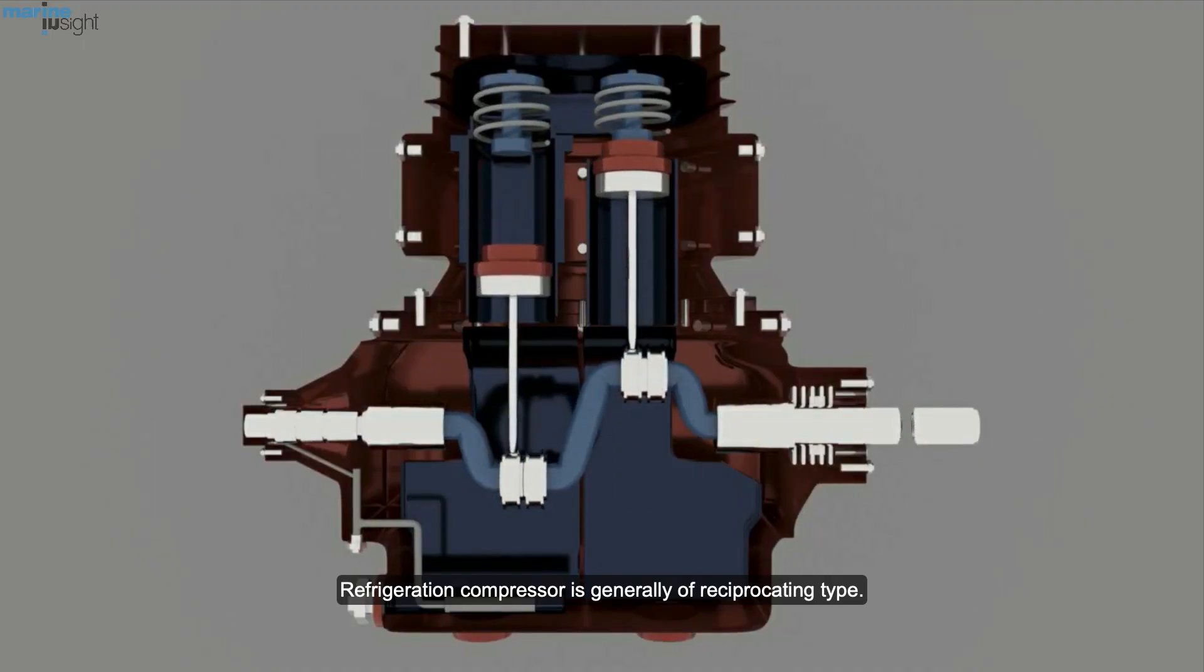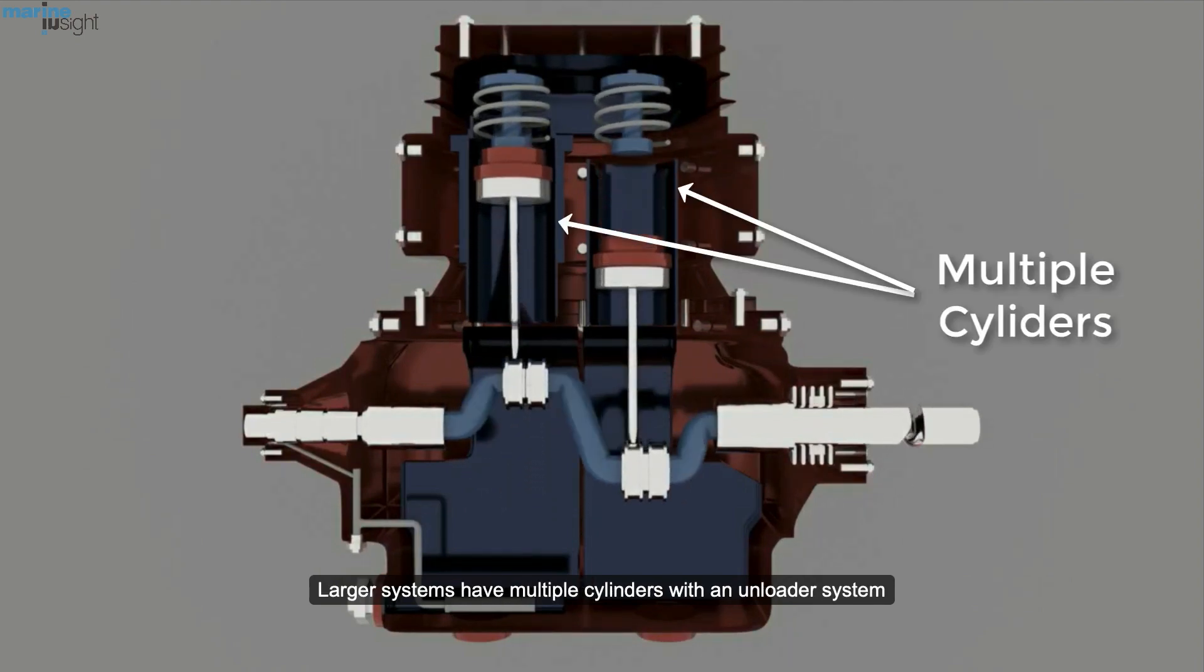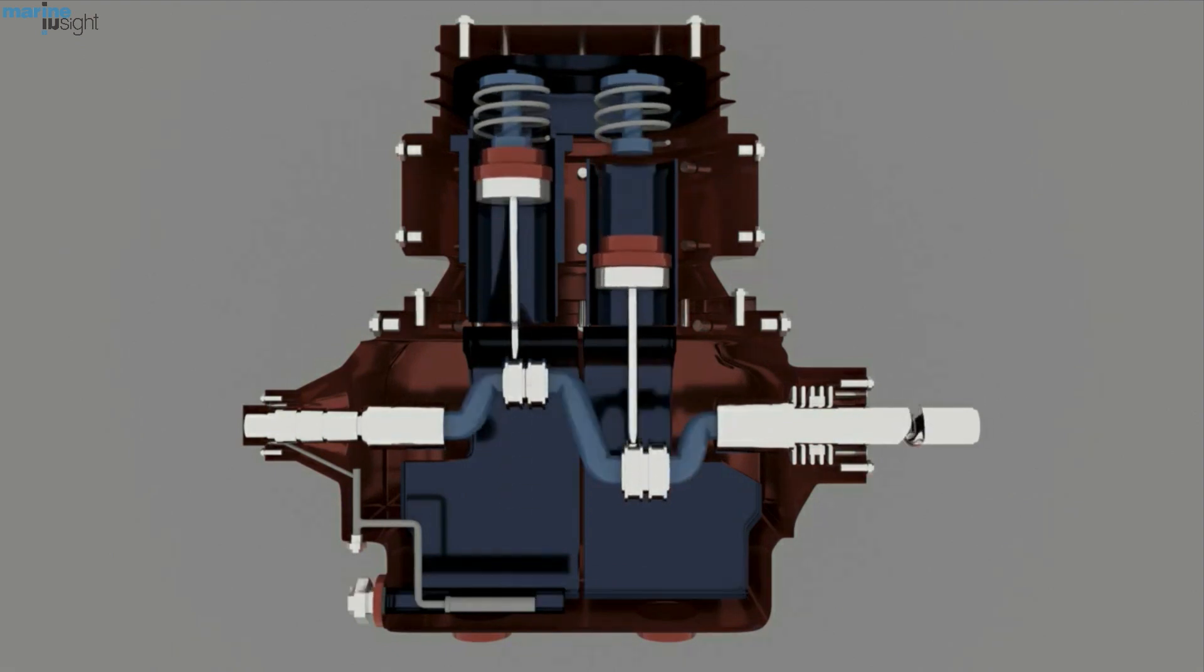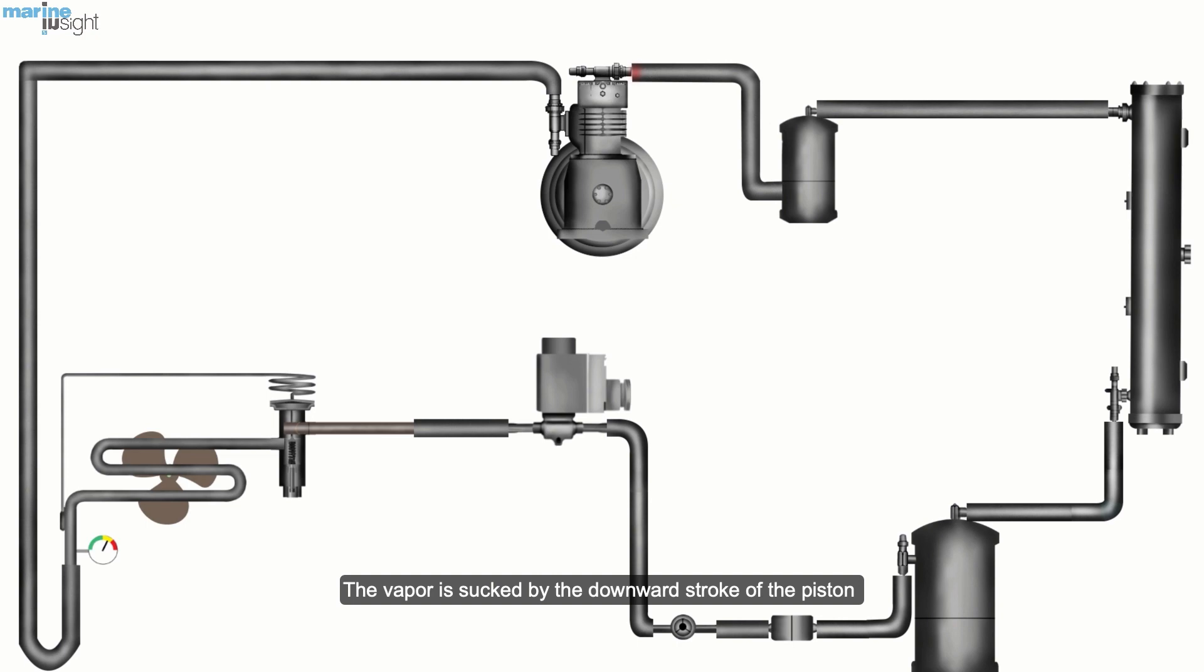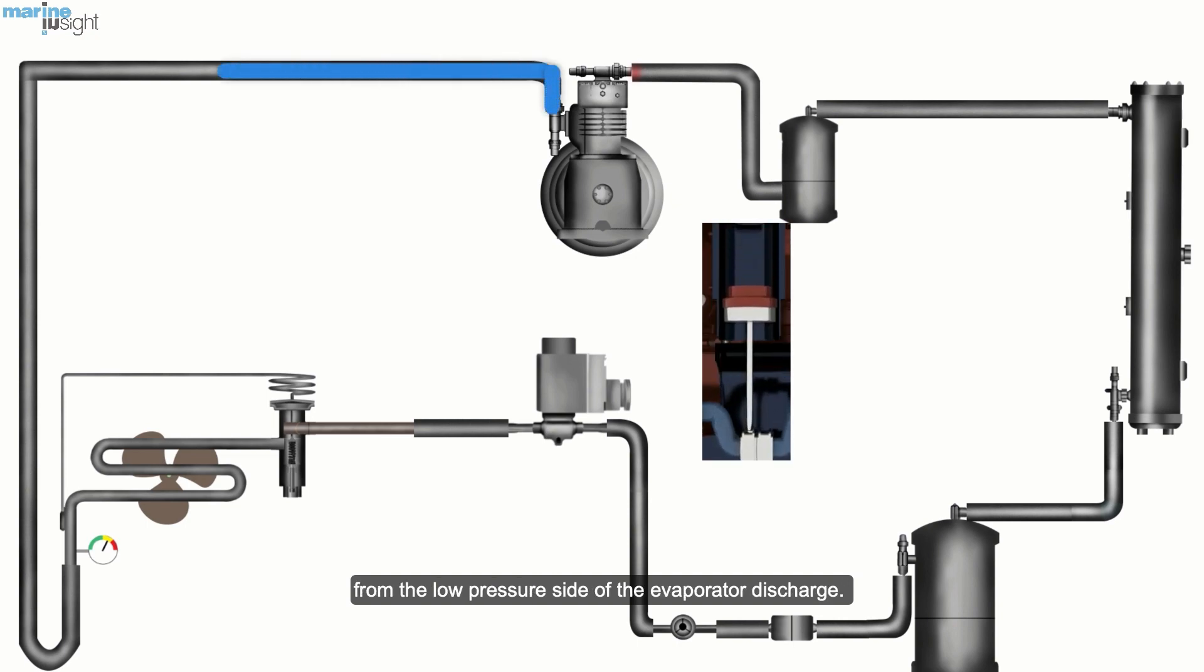Refrigeration compressor is generally a reciprocating type. Larger systems have multiple cylinders with an unloader system using the suction pressure as its signal. The vapor is sucked by the downward stroke of the piston from the low pressure side of the evaporator discharge.